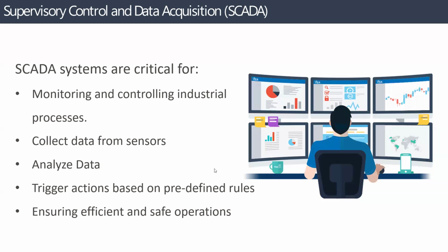The SCADA will take the measurement, analyze it, and then take an action based on this data. As in the example we just mentioned, if the tank level reaches 90%, the command or action will be taken to stop the pump. It can be configured to take this action as a control, or the operator can take the action by himself. And finally, it will ensure safe operation. So the operation will be safely controlled and monitored via SCADA.